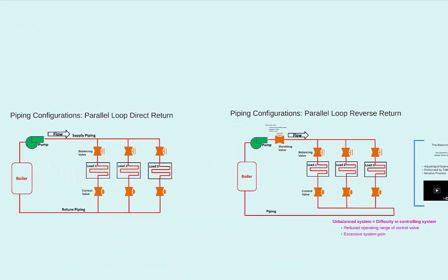So it is easy to see that a parallel loop reverse return configuration has many benefits, especially when it comes to the balancing process. But these types of piping configurations also require a lot more pipe, which is an added cost during construction. Therefore, you will often see, even in new construction, hydronic systems which exhibit a direct return piping configuration in some portions of the system, while other portions of the same system exhibit a reverse return configuration.